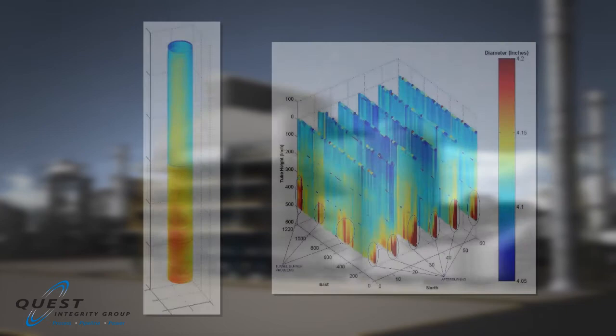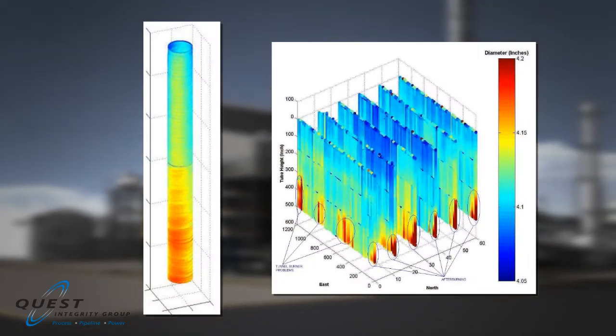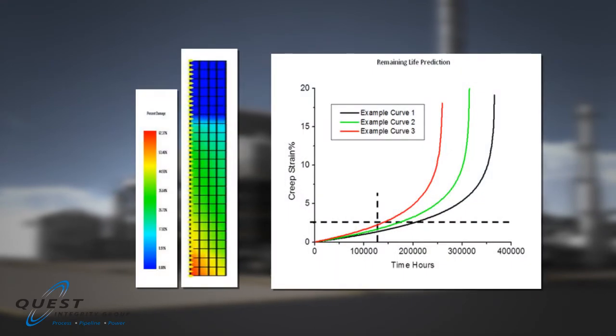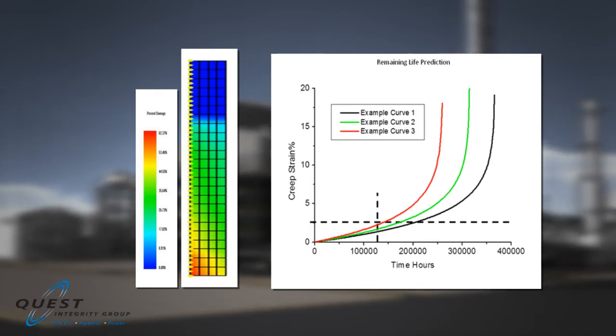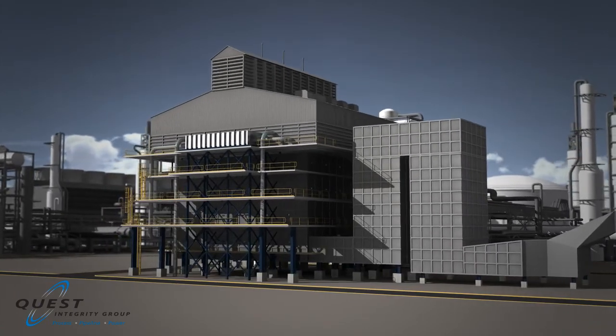Depending upon the level 1 assessment results, an in-depth level 3 remaining life assessment may be necessary. Quest Integrity's proprietary materials database and extensive metallurgical expertise is leveraged in both assessments. The inspection data, advanced engineering, and remaining life assessment capabilities enable tube harvesting and financial planning for future tube replacement.